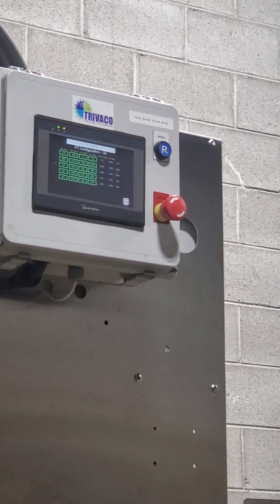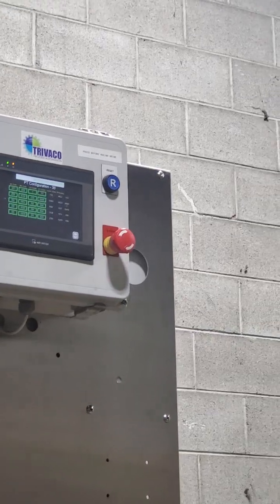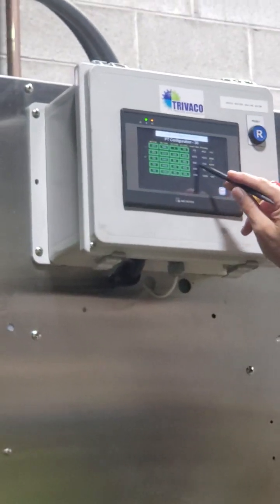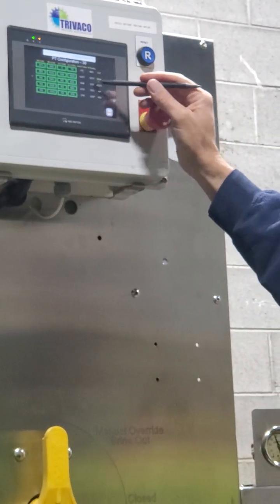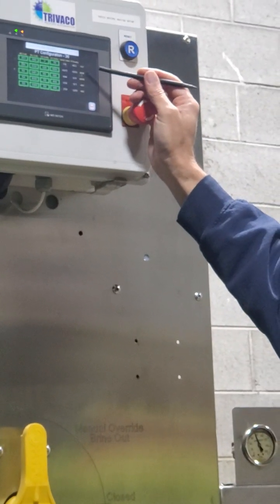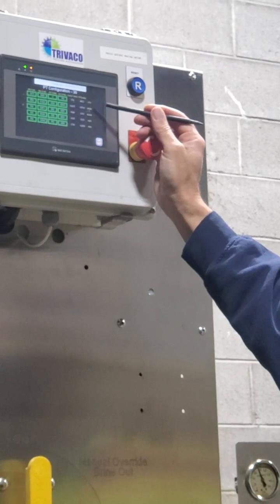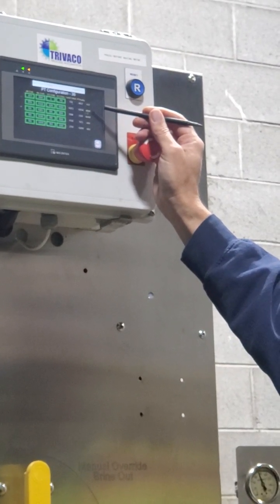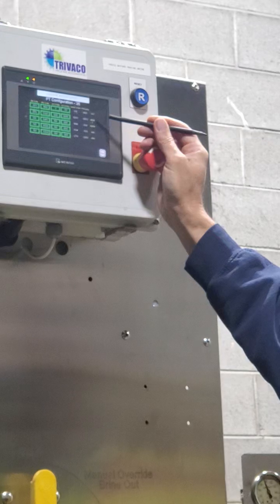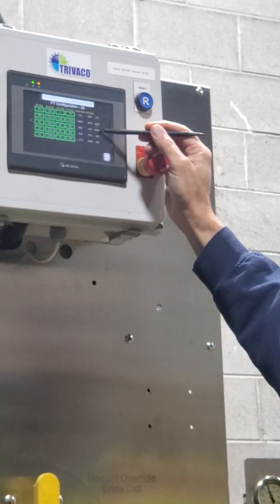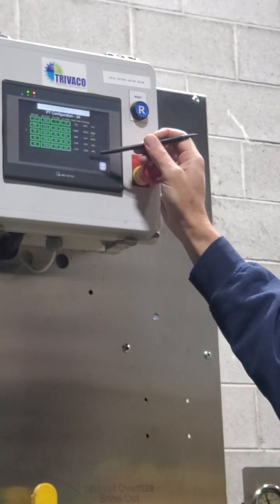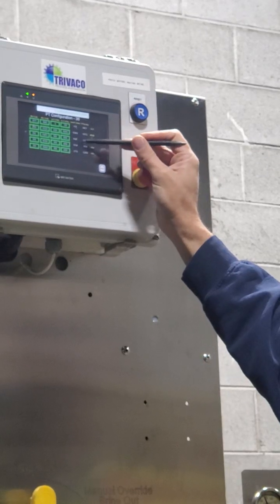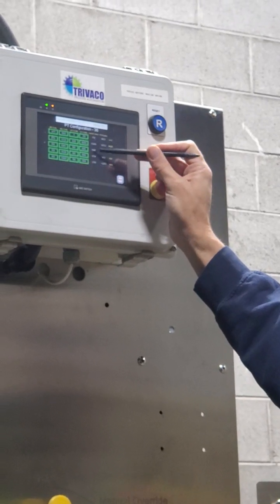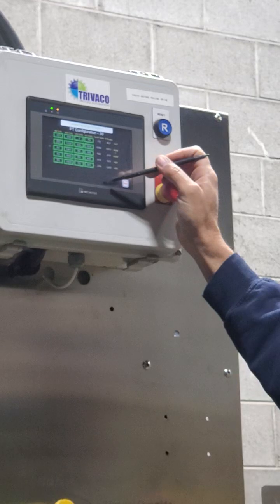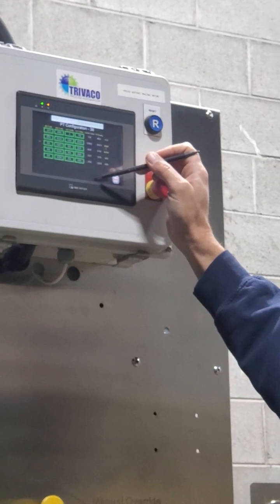So what is the one we just put on today? Can you see the PT reading? Yeah, it's got 3,300 for a reading, and now that number went down. It went down big time. So there must be a leak in there. Now we're getting real world troubleshooting here. Let's watch that number for a little bit, because that was at 3,000. Looking at the tank though, on the side, it looks like it's just under 3,000.